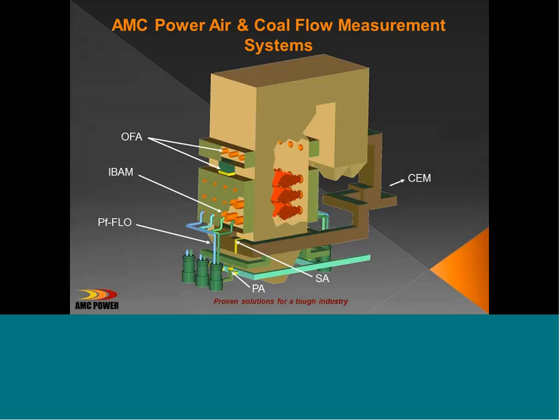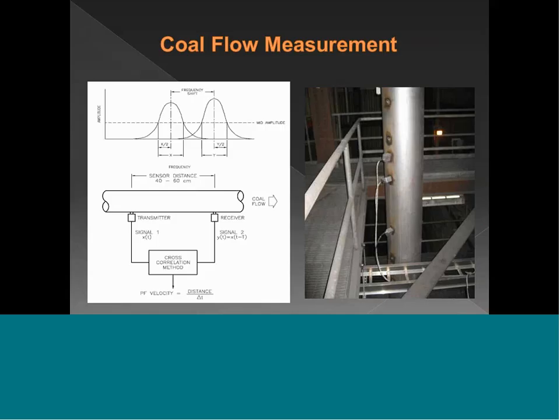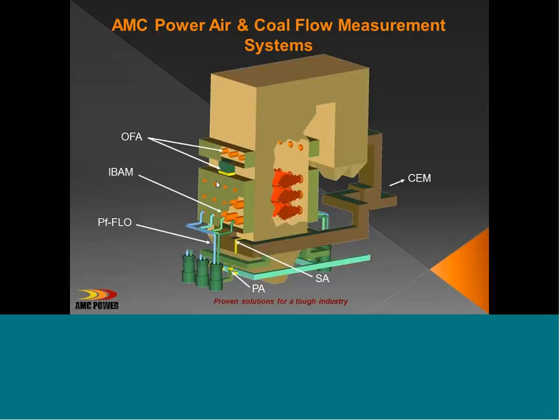And typically you're at a high 2.6, 2.8% excess O2, which is 20-some-odd percent extra air to this furnace. And in the good old days, all that extra air went into the combustion zone right here in the windbox. But overfire air is a tool that's been used more in the last 15 years for reducing NOx. Overfire air runs about 20-25%. And if we leave our O2 measurement where it was, at 2.5 to 3%, all that extra air that we had in the combustion zone is now being run up here to the overfire air zone. So if we have a rich burner or a lean burner running down in this area, it's not as likely to be forgiven.